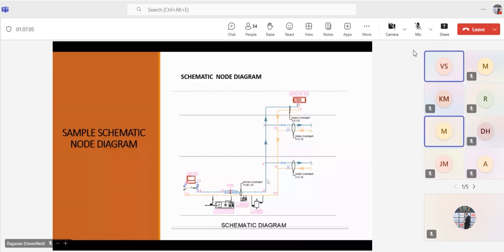Yes, for the flow, how to calculate this one: the flow is based on the heat load calculation. Based on that, you will get the flow rate. Once you get the flow rate, you have to make a schematic diagram to do this calculation easily, or else a flow diagram or flow plan is also okay. But with a schematic diagram you can easily place the fittings. The fittings are mainly the concern, because some people miss the fittings, and that will also impact the overall system efficiency.